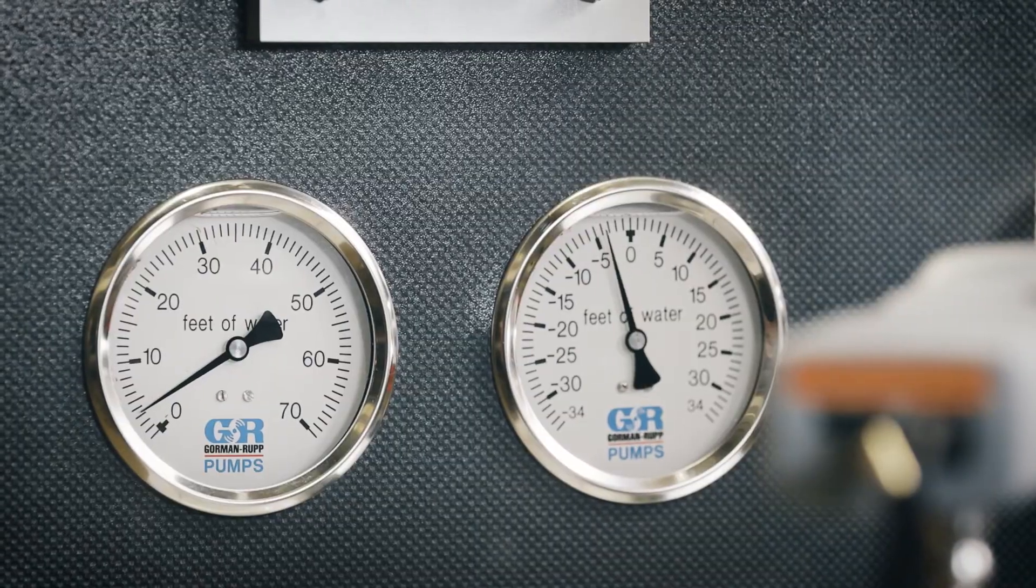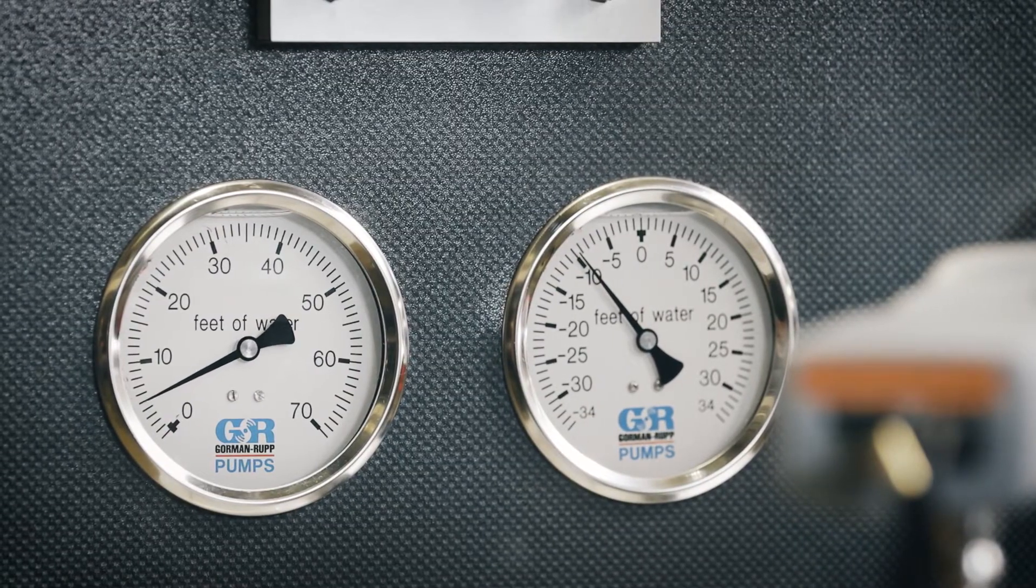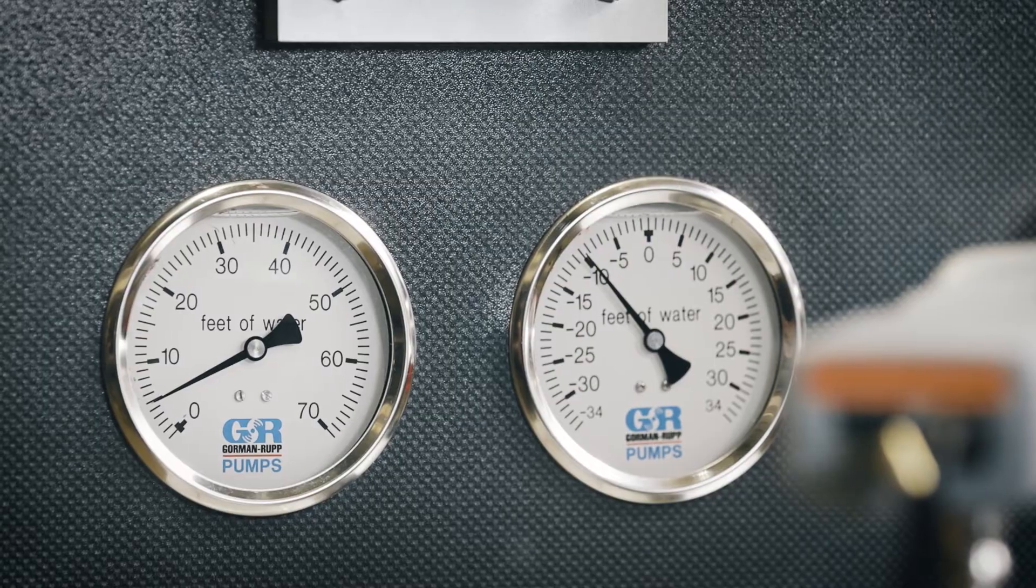For each foot of vacuum the pump generates, atmospheric pressure will push the water up the suction pipe by one foot.